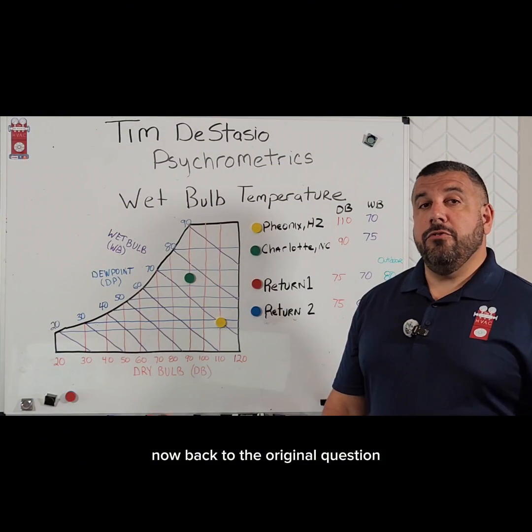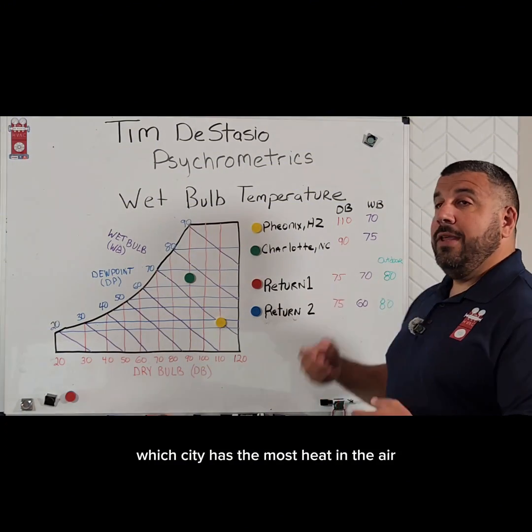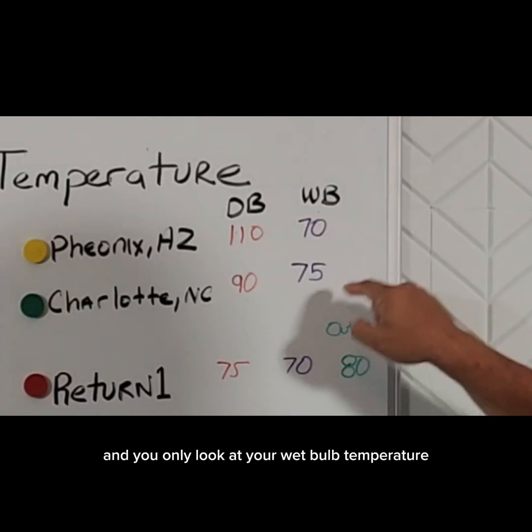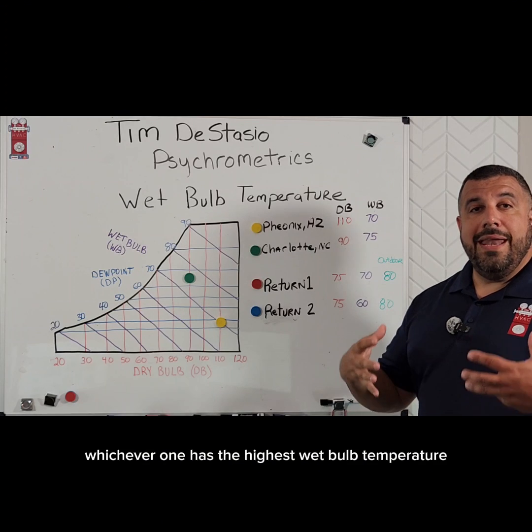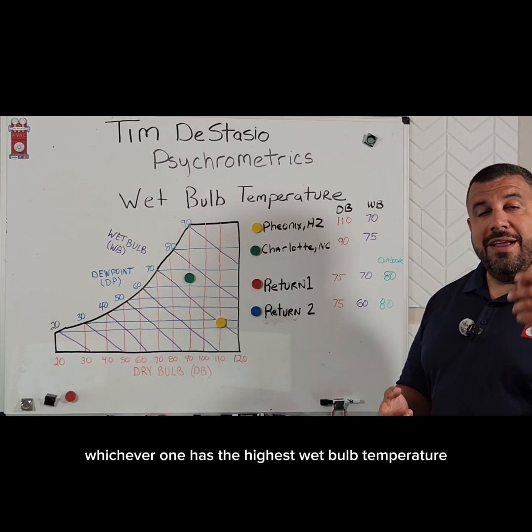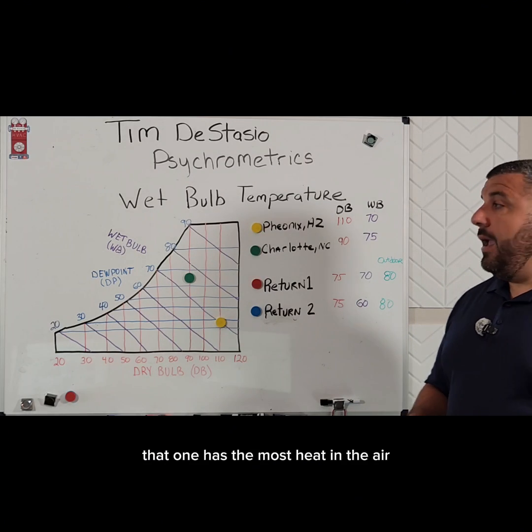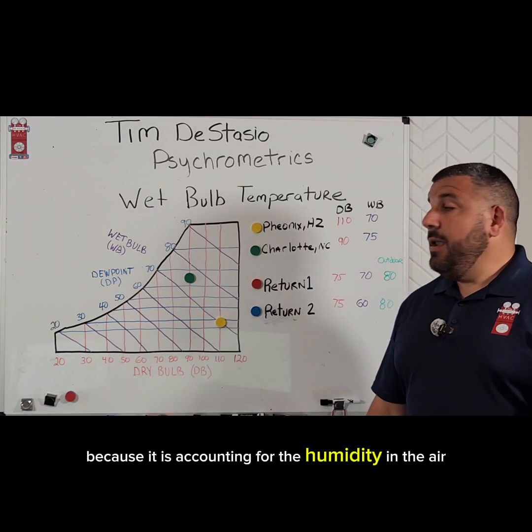Now back to the original question: which city has the most heat in the air? Well, you can actually ignore the dry bulb temperature and only look at your wet bulb temperature. Whichever one has the highest wet bulb temperature has the most heat in the air, because it is accounting for the humidity in the air.